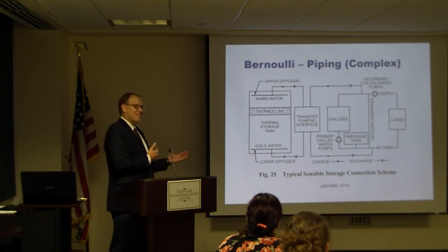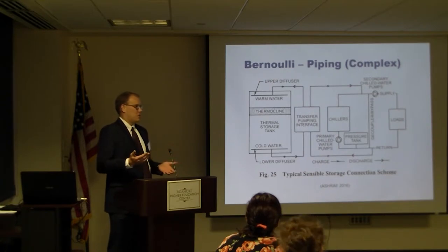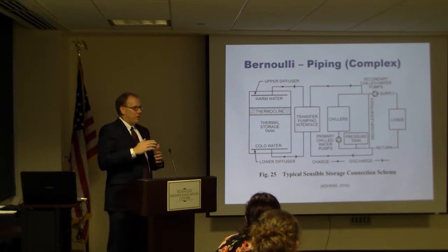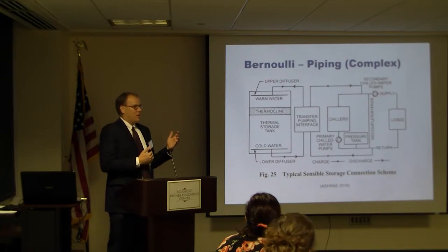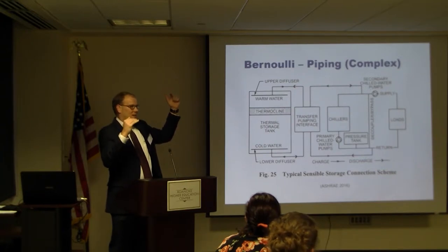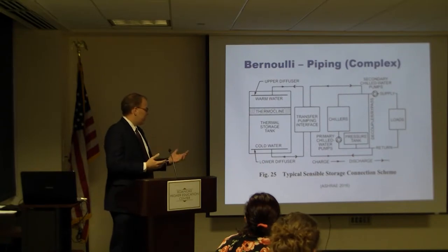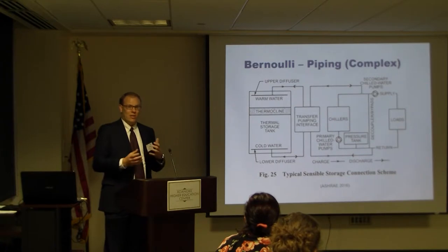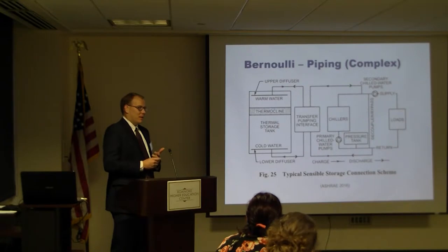This creates some complications on the fluid side from a pumping system. For example, most chilled water storage tanks are about 30, 40 feet high, some of them are taller than that. Once we attach it to a building that's 100, 120 feet high, now we're having to figure out how we manage water that needs to be 120 feet above. If we get over 120 feet above in this tank, we're going to start overflowing the tank right away. So with the complexities involved with the thermal energy storage tank, we tend to look at pressure reducing valves, how we're managing the pressure in the system so that we don't overflow the tank, but we keep the building satisfied.